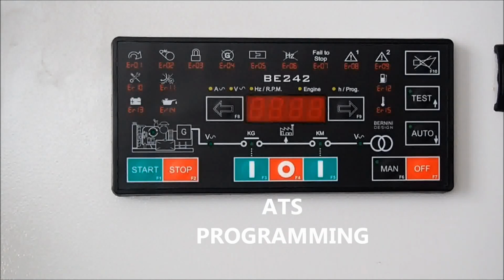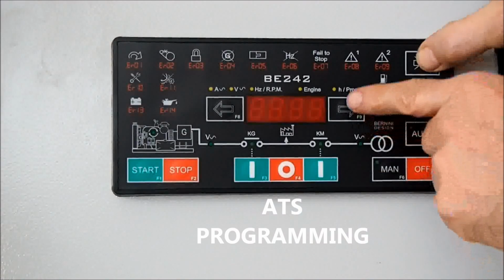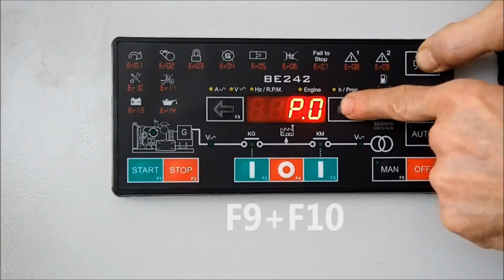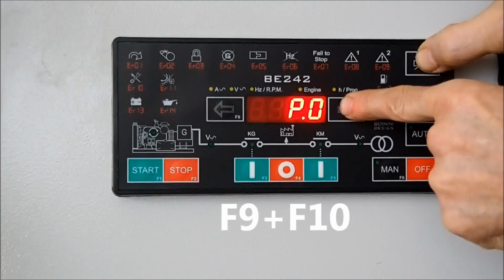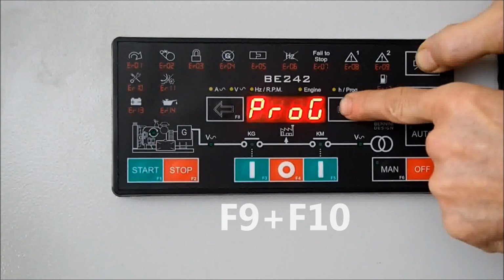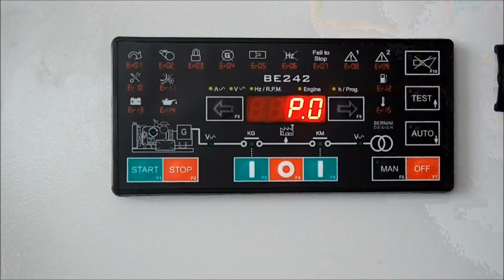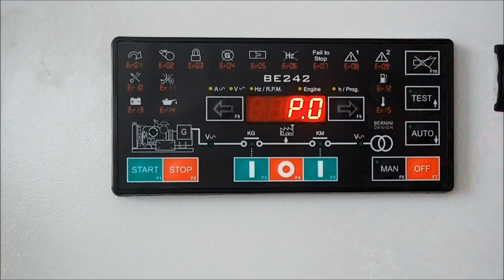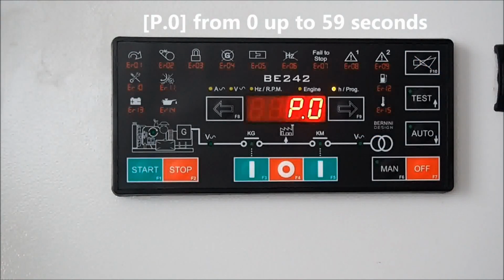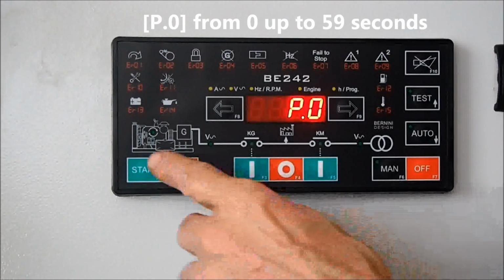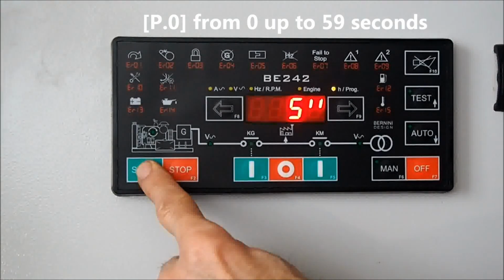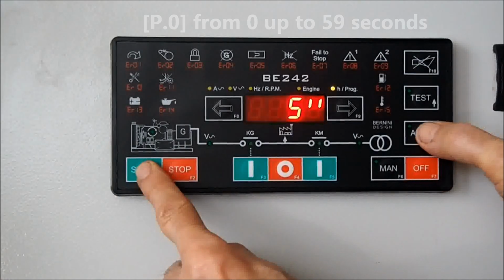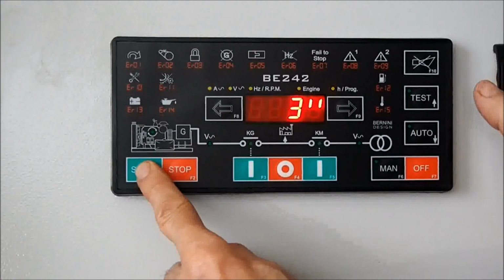Hello, ATS programming roadmap. Push F10, F9 for a few seconds until the message "prog" appears on the display. The yellow LED blinks. First parameter is P0, that is the mains contactor bounce delay timer. Default is 5 seconds. You can put 3 seconds.